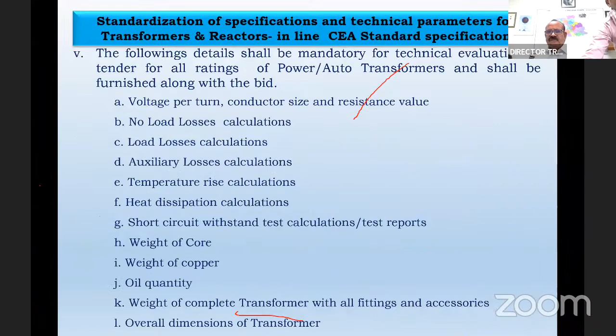We have some issues with the transformers also. Some of those procured have failed within 5 years. A sizable number of transformers have failed, and when they are opened, the process of manufacturing has to be taken into account. These are the issues that have been found in the transformers when opened at our field. There was a thermal fault in the transformer. We opened it, got it corrected and put the transformer into service.